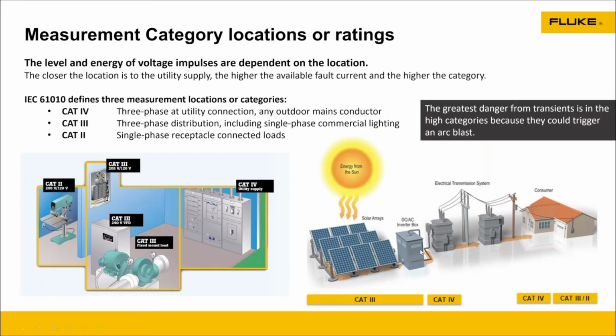And part of that is learning your category ratings. So we talked earlier about your PPE category ratings and the potential energy you were working around. What type of PPE should you have on to keep your body protected? But when you're out in the field and you're trying to choose a meter that might be appropriate to that, we've got to know what category environment we're working in. When we think about category 4, we think about utility. This is on the utility side. This is where we don't have a lot of protection out there. So there's a lot of potential energy out there on those main conductors.